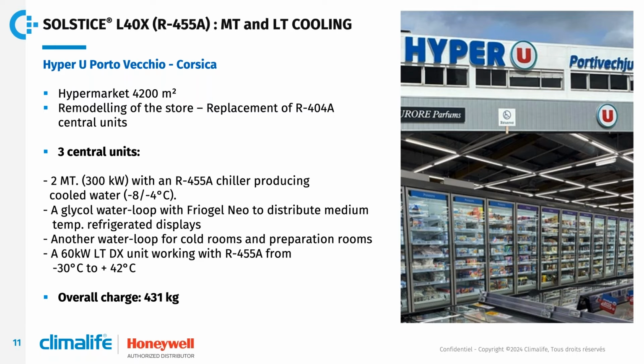Technically speaking, 3 centralized units have been installed here. 2 centralized for MT needs, approximately 300 kilowatts. It was a chiller producing cold water at -8, -4 degrees C, and distributing cooling to display cabinets and medium temperature cold rooms. The third machine was in direct expansion, having roughly 60 kilowatts cooling capacity for LT display cabinets and cold rooms. In this example, please note that the total charge of refrigerant in this hypermarket is around 431 kg only, I would say, and this is very low because of the water loop used for the MT systems.